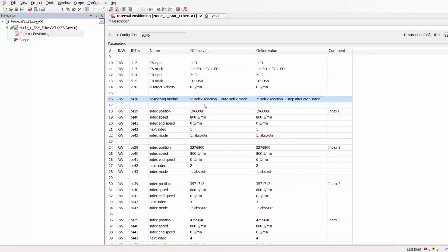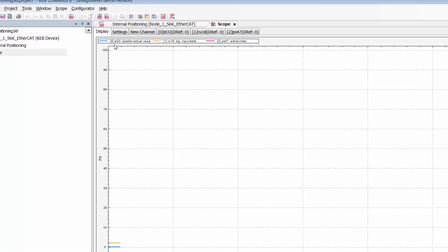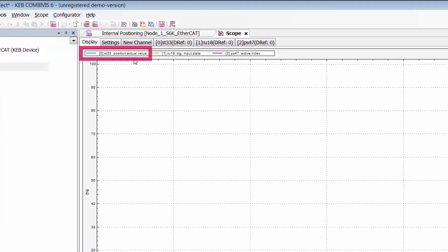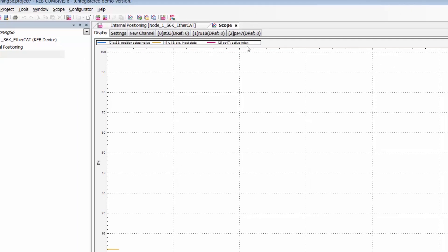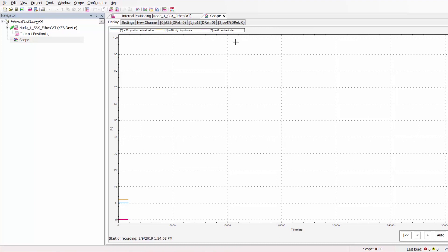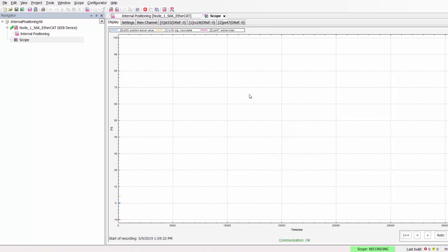For this positioning mode we are actually going to utilize the scope function of the CombiVis 6. This scope was created prior to the video and will allow us to monitor and record three parameters relevant to our positioning profile. We have ST33 position actual value, RU18 digital input state which will show us when a positioning command is given, and PS47 active index which shows us the active index position in the module. Now that we have the scope created we are going to go start scope and then we will begin our positioning.